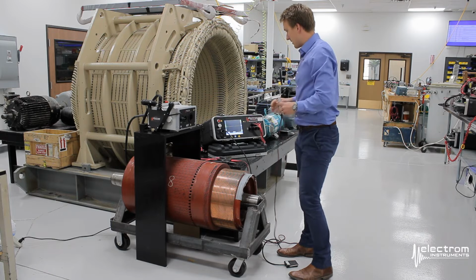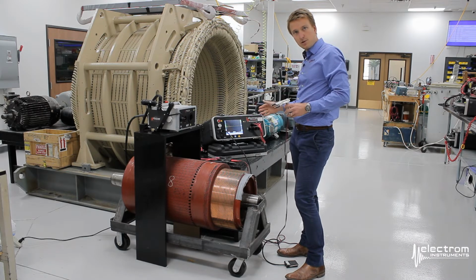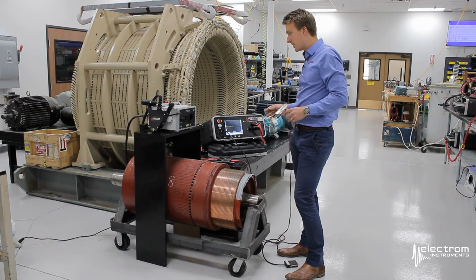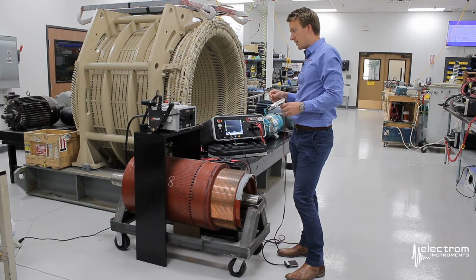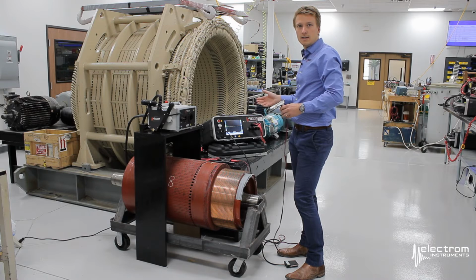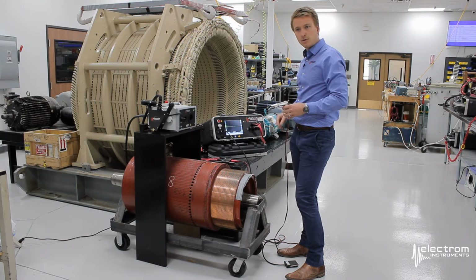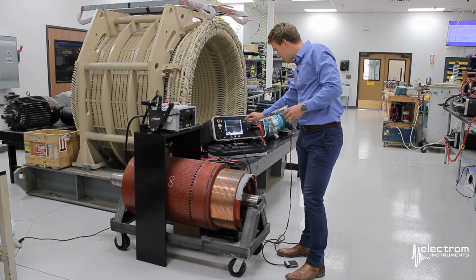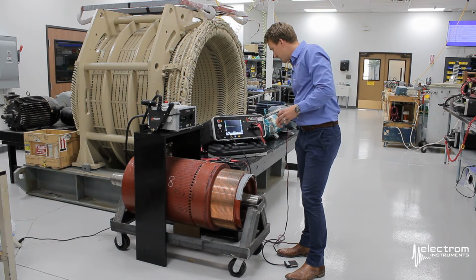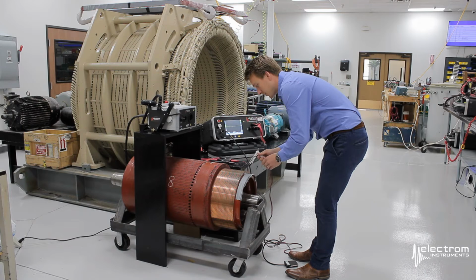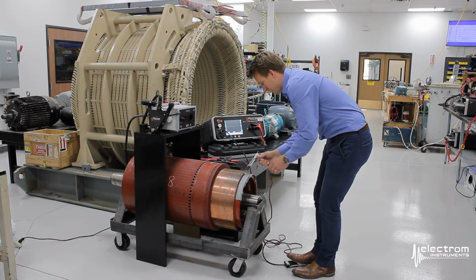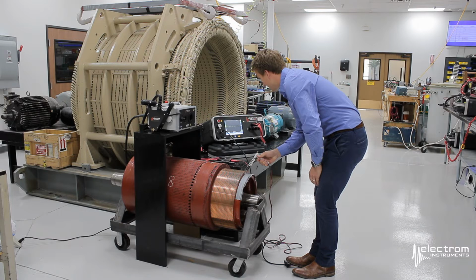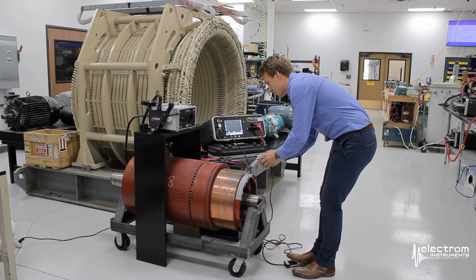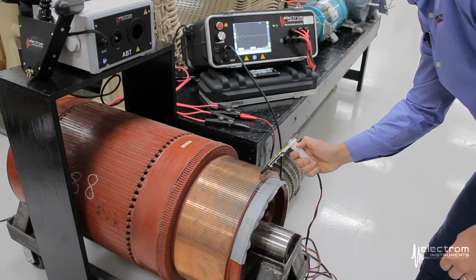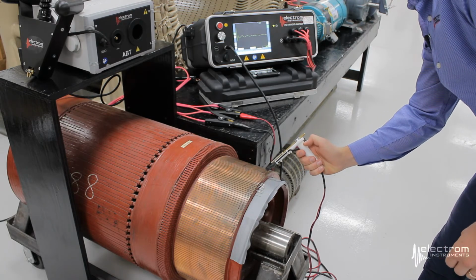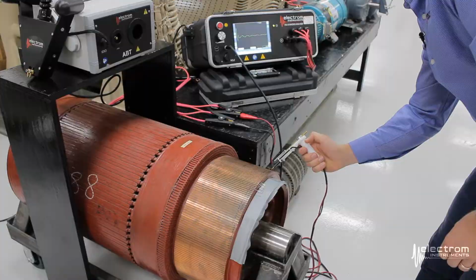You can either use the multi-coil feature, like we demonstrated with the ABT. If you have an iTIG 2 or 3 or 4 B or C model without the multi-coil feature, the trick here is to just select record number 2 and then continue on. So you move 5 bars over and repeat your test set over and over on record number 2. So if you do find a fault, you can save the good waveform and the bad waveform.